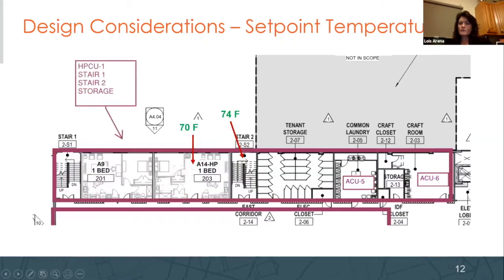You also want to make sure you put spaces with the same heat loads and temperature profiles on the same zone. This is a case where this is a historic retrofit. The stairwells and hallways could not be insulated according to historic retrofit, but the bedrooms are super insulated. So these, if we had them all at the same temperature setting, would be calling for much more heat than the apartments.